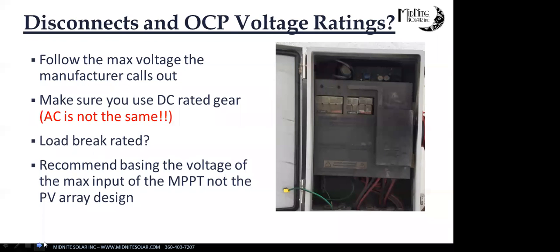So that same holds true. Let's say you've got a 1,000-volt string inverter, but you're only running 500 volts into it. Don't use a 600-volt combiner, because if somebody comes behind you and doesn't pay attention to all the parts and components, they could run that PV array up over the 600-volt limit, and you could run into trouble. So my long and short point is that I like to design the system around the voltage of the MPPT device, whether it's an inverter or a charge controller. If it's a 250-volt Classic or a 300-volt Outback or whatever the case may be, I like to design everything upstream of that around that voltage, and that way there's no surprises if somebody does anything to alter the array.